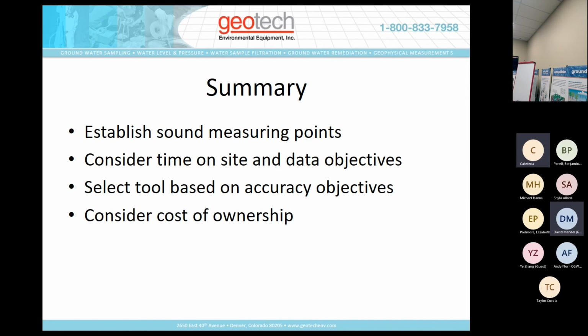It's liquid. Yeah, so the key difference, and we didn't go into any of the interface products today, interface products rely on fluid conductivity to differentiate between product and water. So with an interface probe, product is non-conductive. So some other mechanism in the probe itself is telling you there's a fluid because it's either breaking a plane of light on a prism, or there might be a float mechanism with a float switch. But nonetheless, the conductivity of the water is the key thing in a standard water level meter. So if you go to a sonic, it's going to bounce off whatever that surface is. If there's a 100th of a foot of product or 10 feet, it's going to give you that top layer.